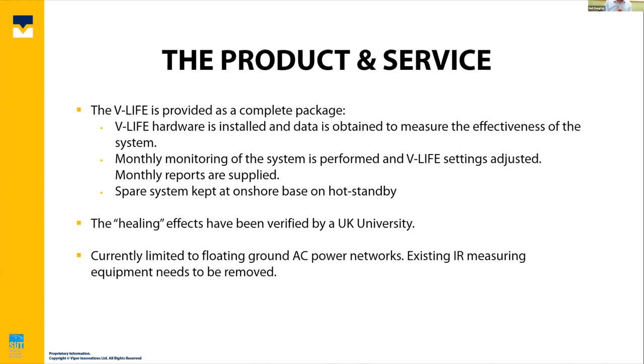What I haven't told you yet is what V-Life does. I'll show you some scanning electron microscope pictures, but it effectively finds the hole in the cable or where water is getting in. It drives the water molecules out through an electrokinetic technique. And then we use an electrochemical technique to create a precipitate to block the hole. So effectively, we are healing the cable by blocking the hole where the water is getting in. As I've said on the final bullet point there, it is limited to floating ground, i.e. IT systems. So that fits very well with the norm of subsea systems.